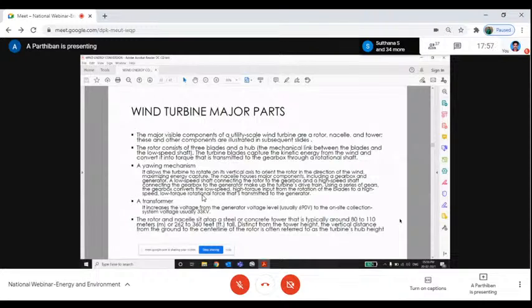The rotor is the part that combines the three blades with a hub. It is a simple one: three blades coupled with a hub is called the rotor. Next is the nacelle. The rotor is coupled with the nacelle, and the nacelle has the major components: the gearbox, generator, and transformer. In olden days, the transformer was at the bottom of the tower, outside it, with a separate yard for the transformer, breaker, and everything.